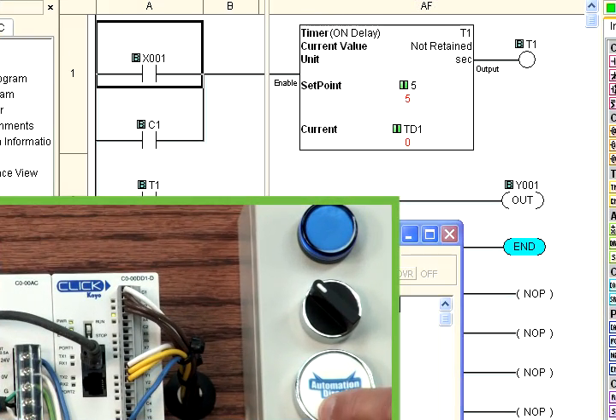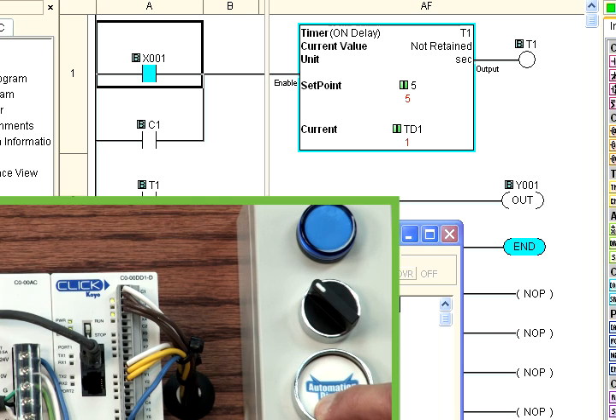Let's try one more thing. You may have noticed we also have an X001 input in our ladder logic that is programmed in parallel to our C1 bit. In our demo unit, we have a push button wired into X001 and also an indicator pilot light wired to output Y001. If we press the push button and wait 5 seconds, we will see the indicator turn on.